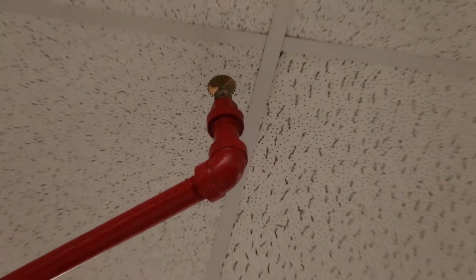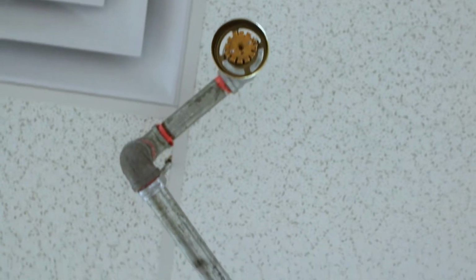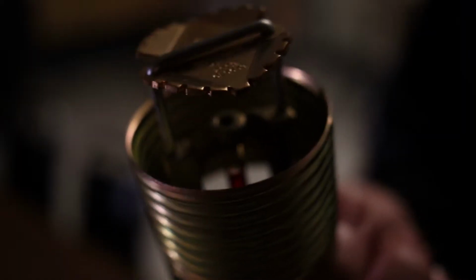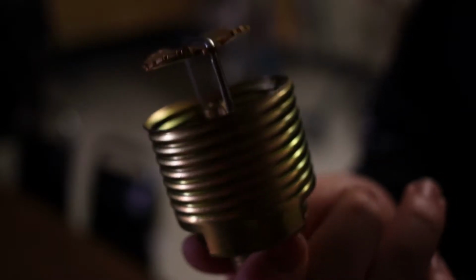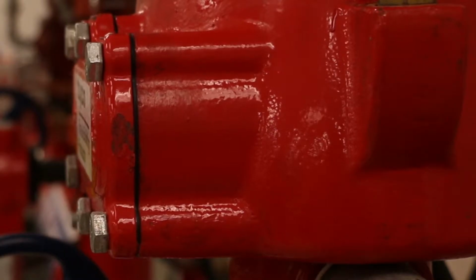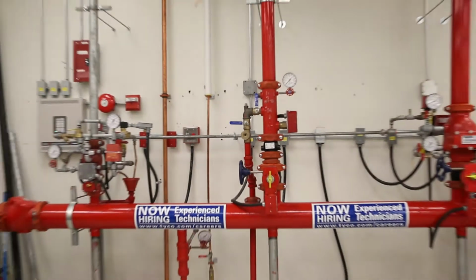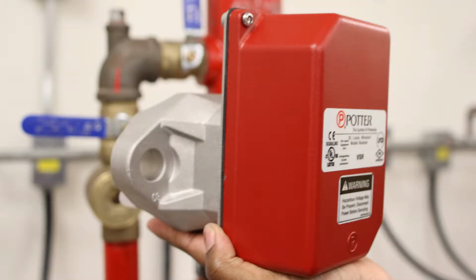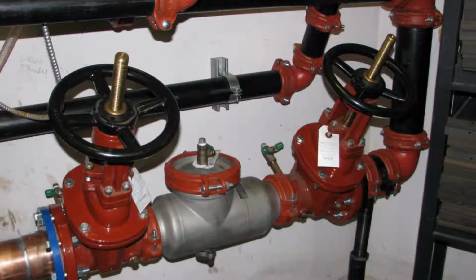Today, this video is going to explain the importance of fire sprinkler system testing. A fire sprinkler system is a fire safety method that protects buildings against fire by shooting water out of the pipes through the sprinkler head activated outlets. We are going to talk about the main components that should be tested that include water flow switches, tamper valves, fire pump, backflow preventer, and the requirements of NFPA 25, the standard for fire sprinkler system testing.